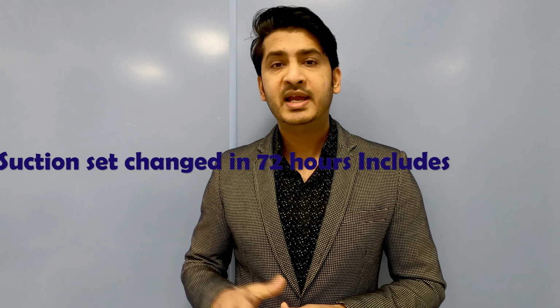There are two types of suction which we use in the unit: high vacuum suction and low vacuum suction. Bear in mind that high vacuum suction should not be used for a chest drain. Low vacuum suction is specially made for the chest drain because we don't require higher suction pressure. The suction set should be changed every 72 hours, including the yellow tubings, the filter, the tubing which connects to the patient, and the closed suction if applicable.